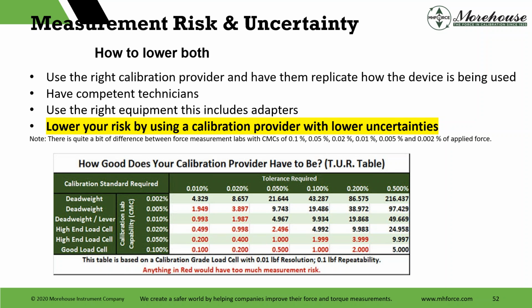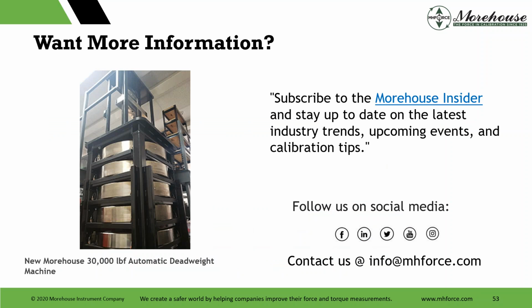But using a better calibration provider will give you the ability to open that car door. It will give you a wider window for uncertainty. Hopefully it will pass more instrumentation, so you don't have those product failures or root cause analyses or the other quality concerns that you may have when a device fails, and you might not have to issue an out of tolerance report and recall a bunch of instrumentation. Also, using a calibration provider with a low uncertainty may allow you to lower your CMC uncertainty as well. It certainly should.